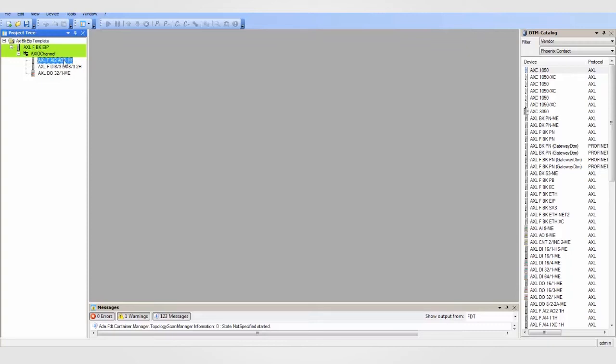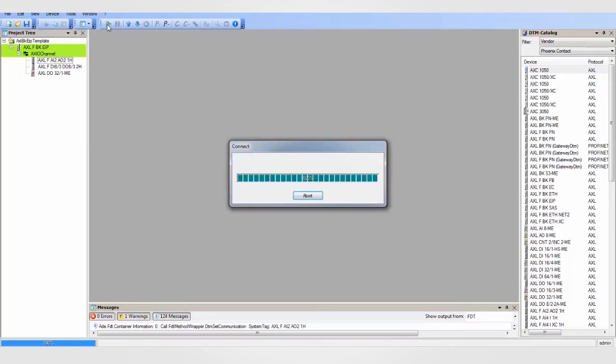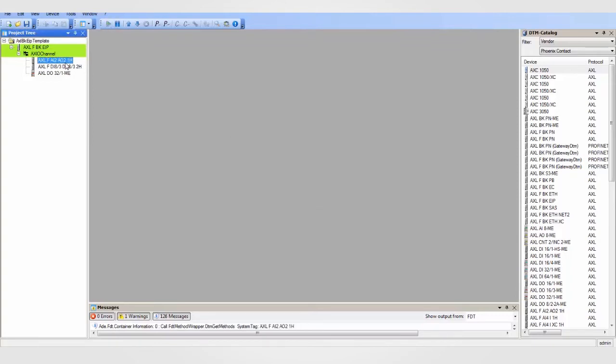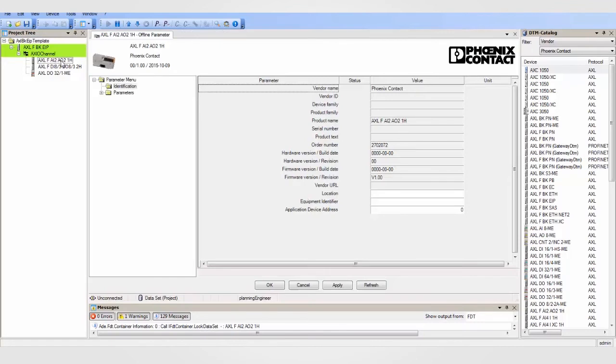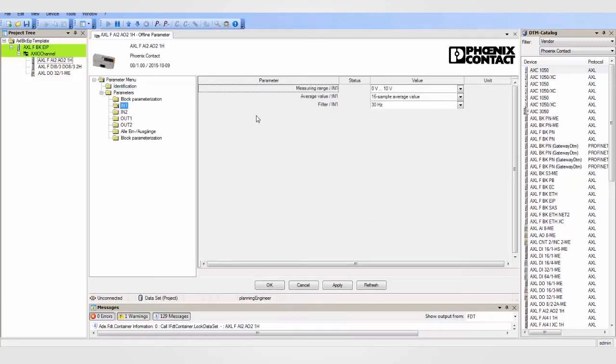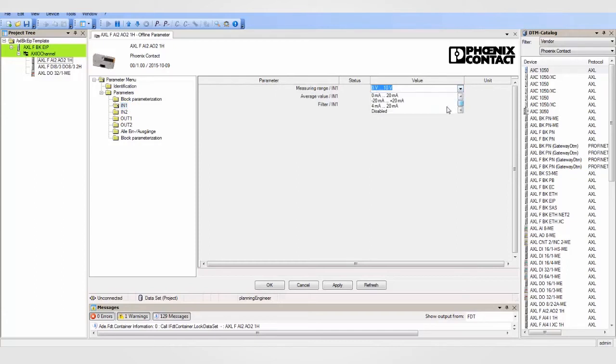To configure the analog module, first highlight the module and then click the green connection icon. To open up the configuration, go back and double-click the module. Under the parameter folders, you will find folders for each of the four individual I.O. channels. In these folders, you will see all the available configuration options. Simply set the channels to the desired ranges and apply your changes.